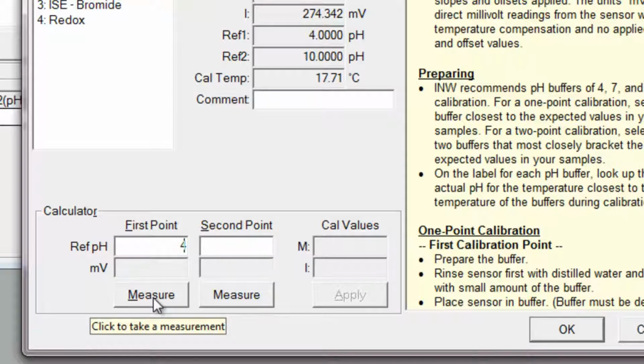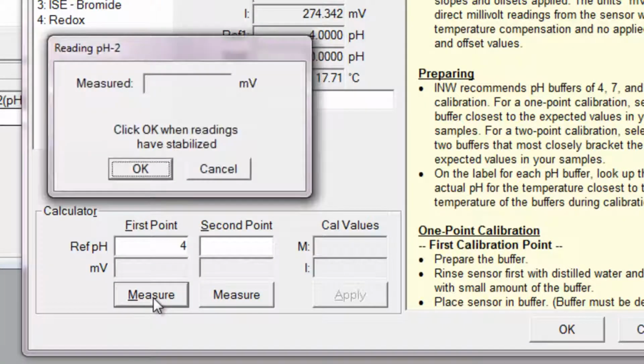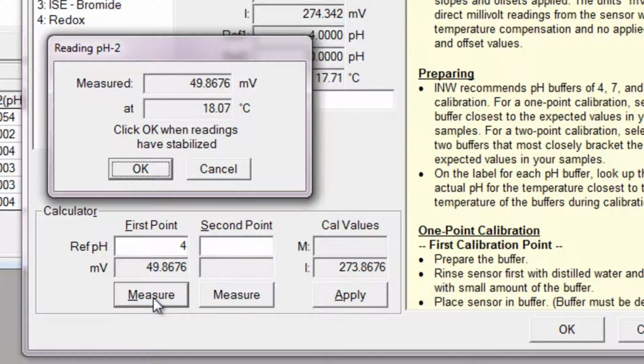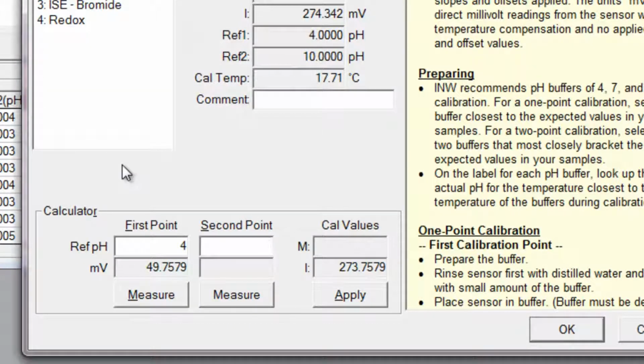In the calculator window, you'll click Measure. And what you'll see here is the raw millivolt output from the probe. And what we're looking for is stability. You'll see that the millivolts are very stable. You might notice it tick between decimals, which is normal in an up and down fashion. You'll also want to make sure the temperature is stable. Once everything looks good, click OK to accept the value, and we're ready to move to the second point.